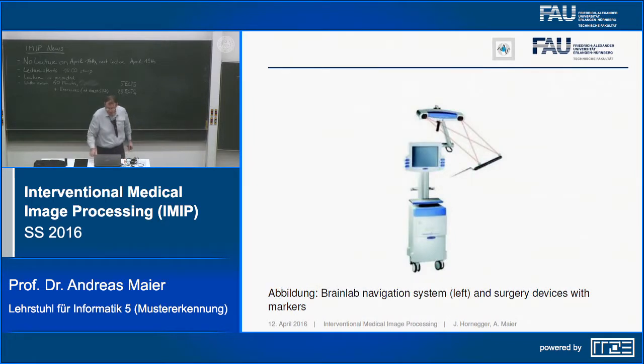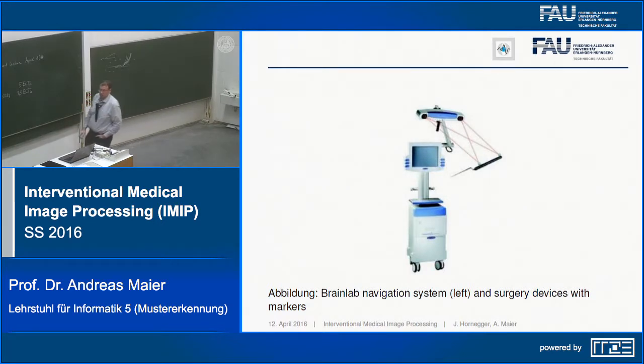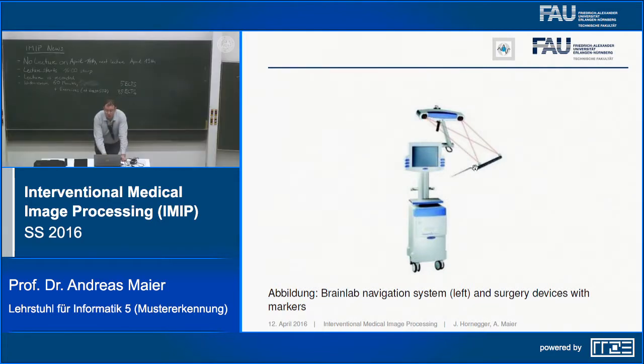Another very nice machine, which is also relevant for minimally invasive surgery, is a navigation system. What this system does is essentially use two cameras. You can see it has an infrared camera here and here, and it emits infrared light. Now you have two small markers on the instrument, and those markers reflect the infrared light, so in the infrared camera you will see two bright spots. You track those two points from two cameras, and then you are able to reconstruct the 3D position of the device.